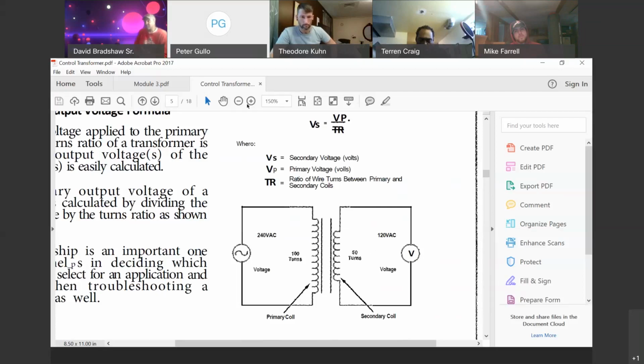One thing I'd like to add: remember, guys, when the turns ratio goes down, like in this example, 100 to 50, you're always going to divide the primary voltage. In other words, you started with 100 but went down to 50. So 100 divided by 50 is a ratio of 2. So you just divide the voltage by 2. 240 divided by 2 is 120. So when the turns ratio goes down, you're just going to divide.